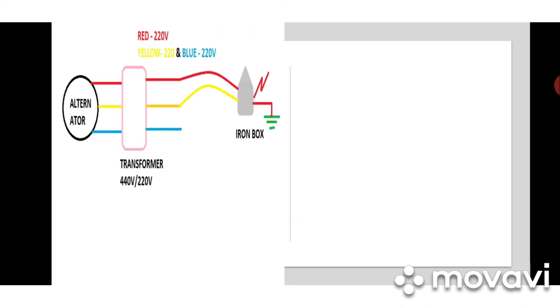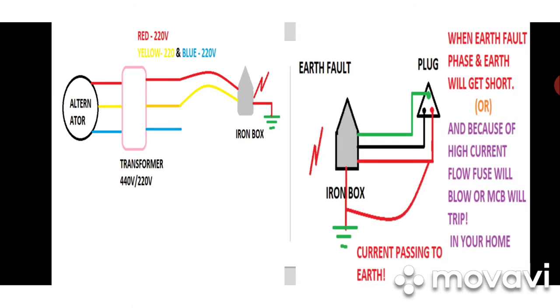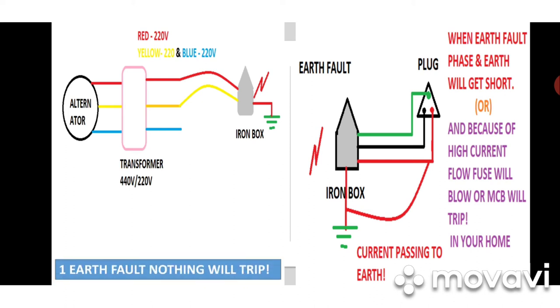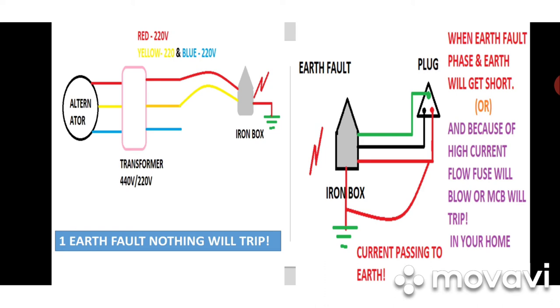Now let's see the advantage of having no neutral — the isolated neutral system. In a home, if an iron box has a fault and current starts leaking, after the iron box touches earth, current flows to earth. A fault occurs, high current flows, and the fuse blows or MCB trips. So even one earth fault will trip the MCB. But in a ship, if one phase touches earth, nothing will happen because there is no neutral.